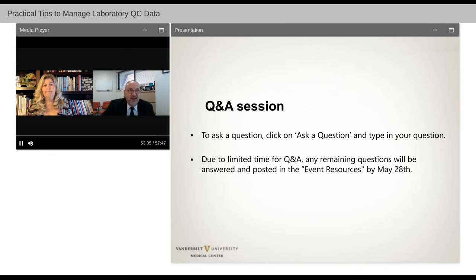So, you know, if you're using that as a failure, you're going to be troubleshooting a lot more frequently than if you used a wider range, like a 1-3S type of rule. But you really need to tailor your quality control rules and pick your quality control rules to the method itself, the performance of that method. Is it a very stable method? You want to probably use wider ranges, maybe fewer rules.